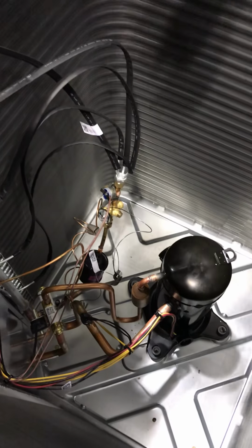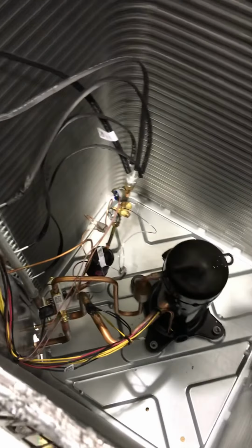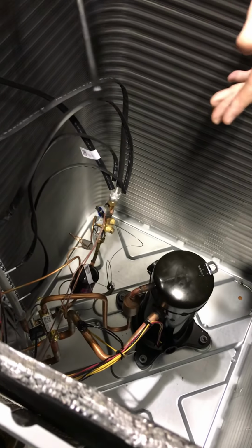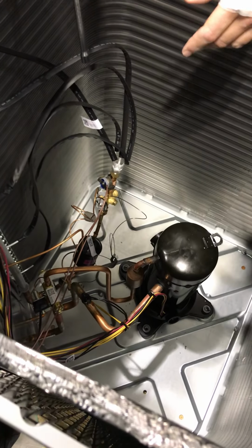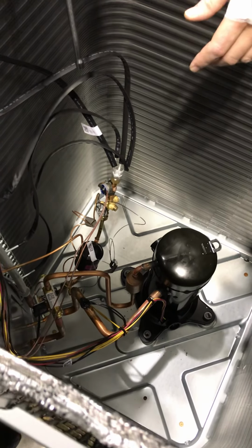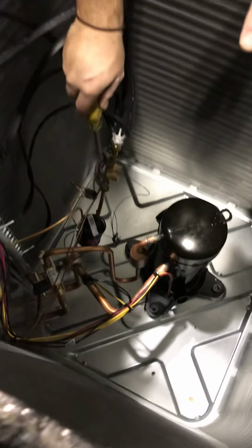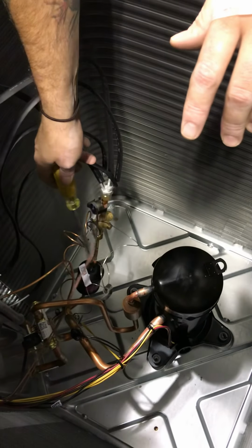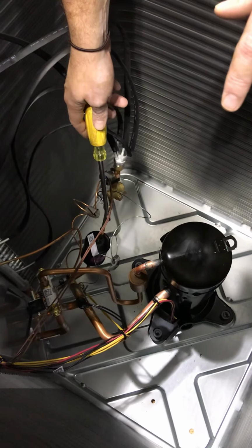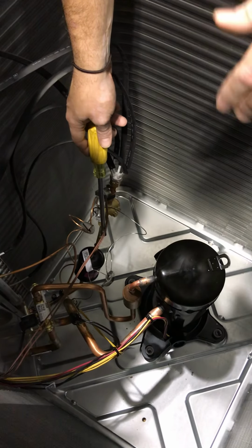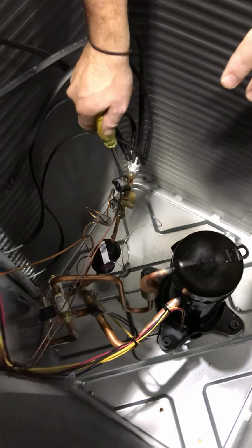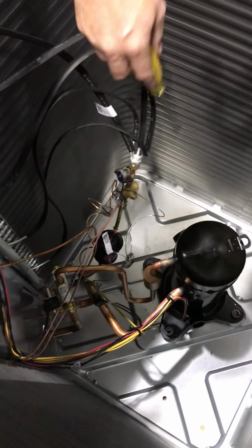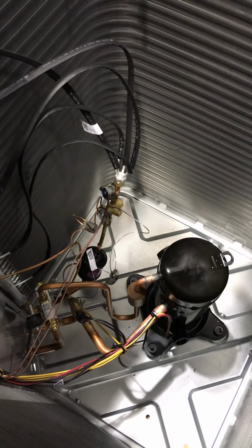Okay, they make devices that I don't have or can't afford that can hook up to this, and it'll tell you everything. It'll tell you the flow of your refrigerant, where it is, your temperatures, and things like that. All right. This is a coil sensor. I've had times where I've had to disconnect these because they were giving us trouble. They were turning units off and kept turning units off. So instead of replacing them, we'll just phase them out, disconnect them.